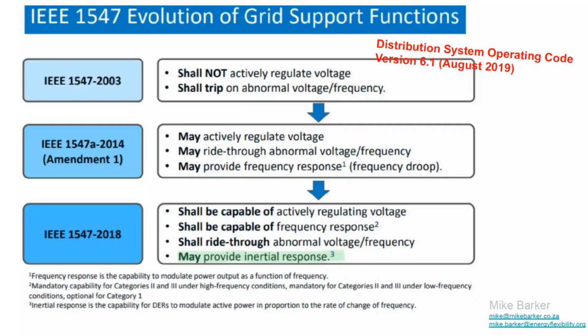But we know that when you have an inverter-rich feeder, you need to start thinking differently. So in 2014 an amendment came out saying inverters may, not shall, may actively regulate voltage, may allow for ride-through, may allow for frequency response. Then in 2018 they started making these issues mandatory. And of course we're waiting for IEEE 1547 version 2025, might be 2026, and that version is going to start providing inertia.